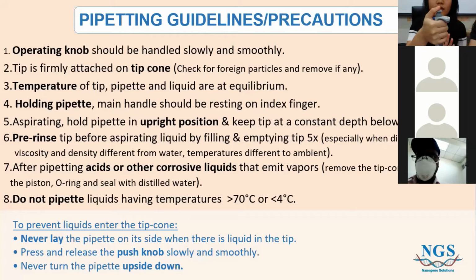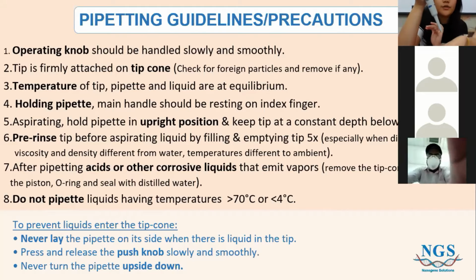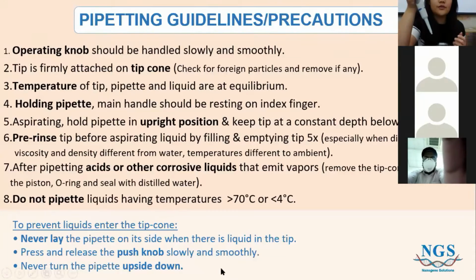First of all, this is the operating knob. Whenever you're using a pipette, make sure that your operating knob is always being handled slowly and smoothly. Don't rush into pressing it. This is your tip cone, and you should always find a suitable tip. For example, this is a 20 to 200 microliter tip, so I'll be using a 200 microliter tip. Every time you're using a pipette, make sure that your tip is firmly attached to the tip cone. It's important to remember that the temperature of your tip, your pipette, and your liquid are always at equilibrium, so always the same temperature.